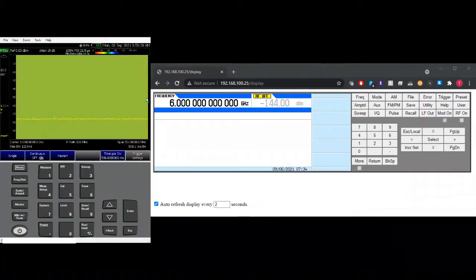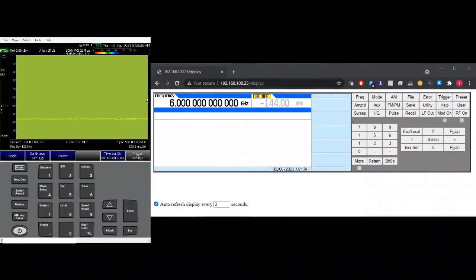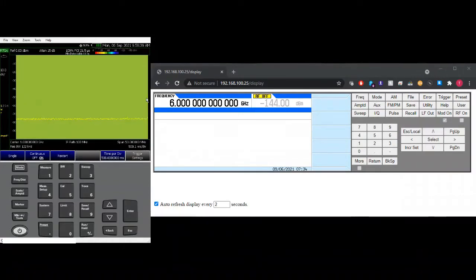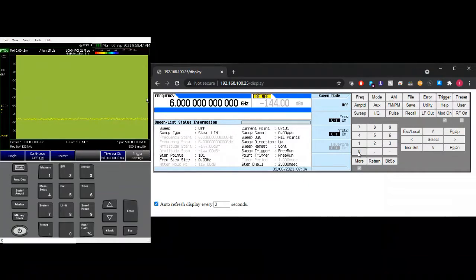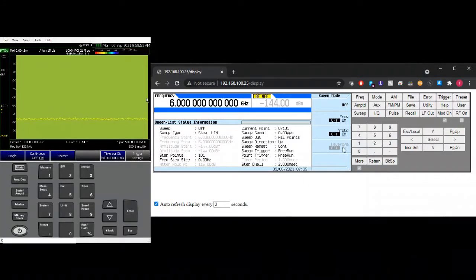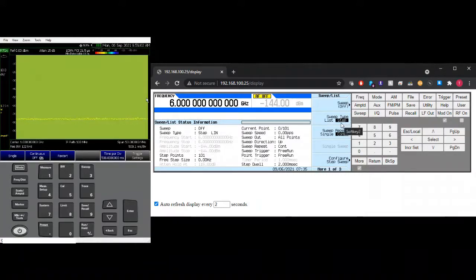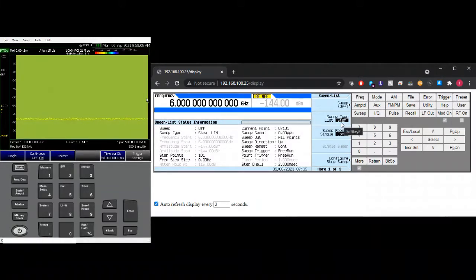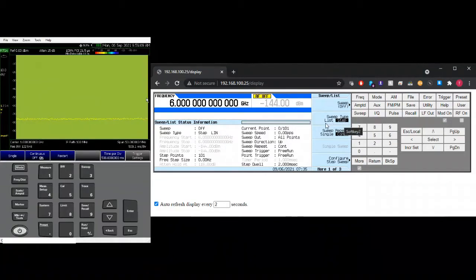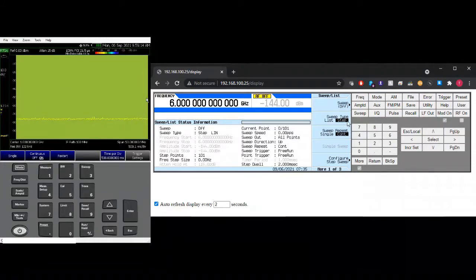So this sweep function is available for both vector and analog signal generators. Most of the time this sweep can do three different types of parameters in one sweep which is frequency, amplitude and waveform. In this video we're going to focus on sweep type step and I'm going to cover sweep type list on the other video right after this.